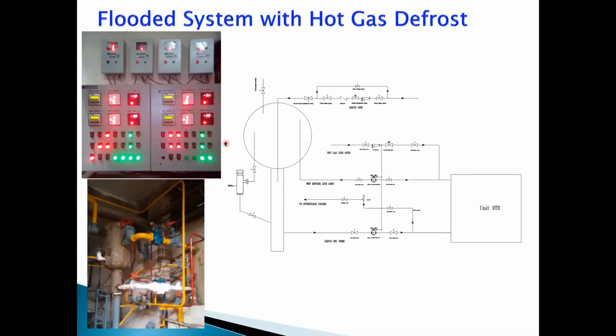And whenever you want to defrost the evaporator, you cut off the ammonia supply, switch off the fans and start water. So water at ambient temperature, around 28 to 30 degrees centigrade, will slowly start defrosting the frost on the coil. But what are the limitations? It's a simple way: have water and drain it.